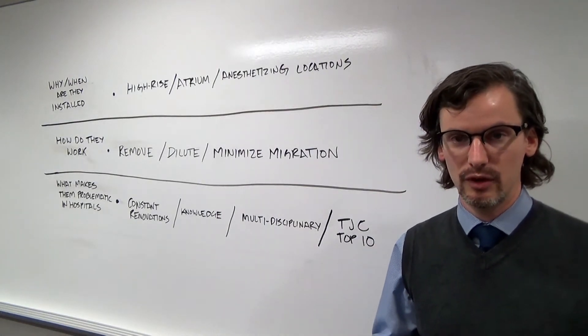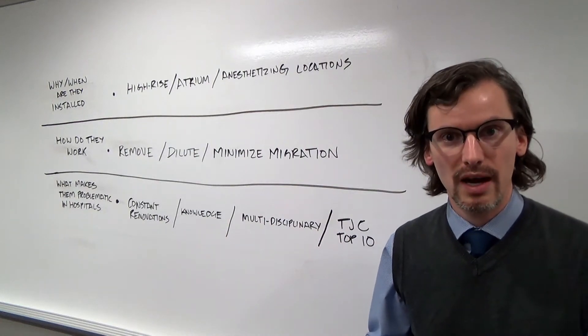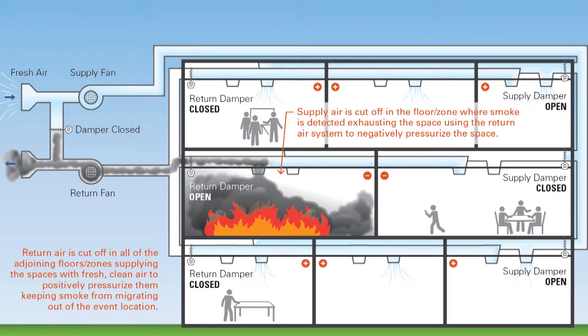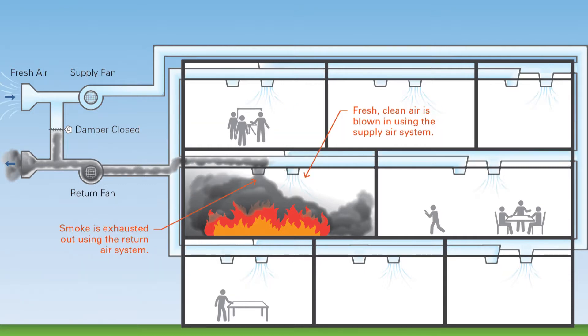There are three basic system functions. You either pressurize to maintain a barrier where smoke can't come into a zone or space, or you exhaust the smoke, physically remove it and discharge it to the outdoors, or you purge the smoke out with fresh air.